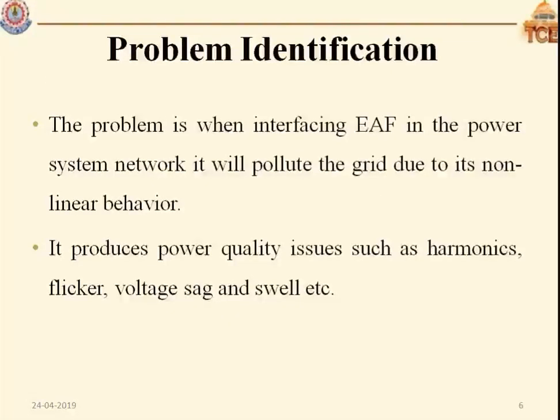The problem identification is that when interfacing the electric arc furnace with the grid, it pollutes the customers who are connected at the utility. It produces power quality issues such as harmonics, flicker, and voltage sag and swell due to large reactive power variations, and during the boring and melting process, it produces more current harmonics.